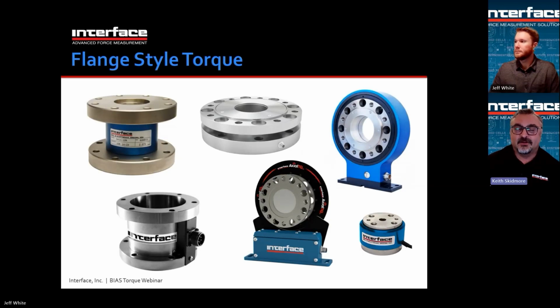Here we are showing some flange style sensors. Some of them have through holes through the middle, which helps accommodate the reaction torque mounting where the motor shaft may pass through the sensor. Some of these are bearingless rotating sensors. So the ATQ, which is in the lower middle, and then in the upper right, we have a T27, which is also a bearingless sensor. Then the rest are reaction type sensors, not intended to rotate. Again, these can rotate, just it's limited by the cable. And so if you, say, had a valve test that's reciprocating back and forth over 90 degrees, a reaction sensor may be preferred. You just have to manage the cable so it doesn't get worn out from moving back and forth.